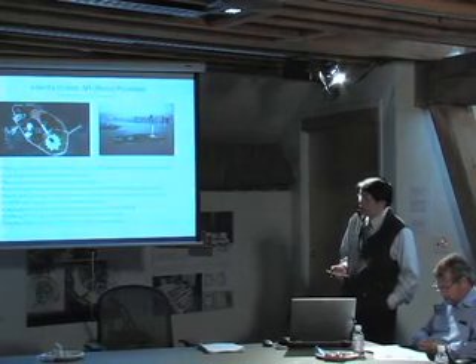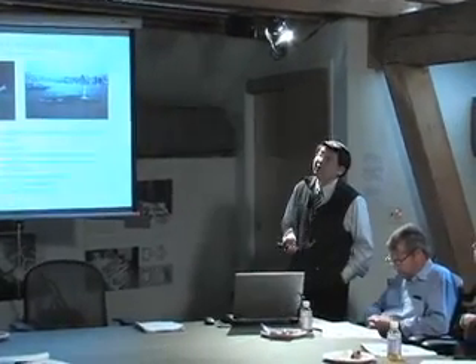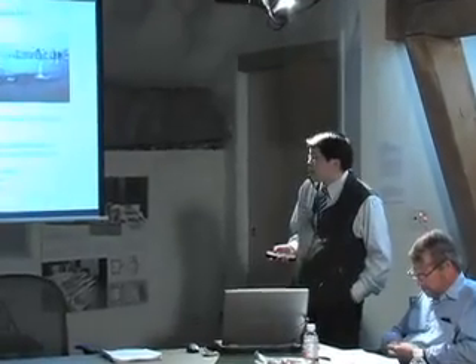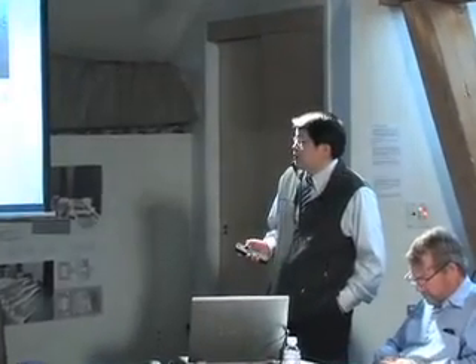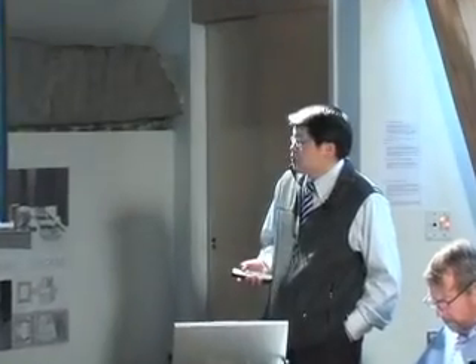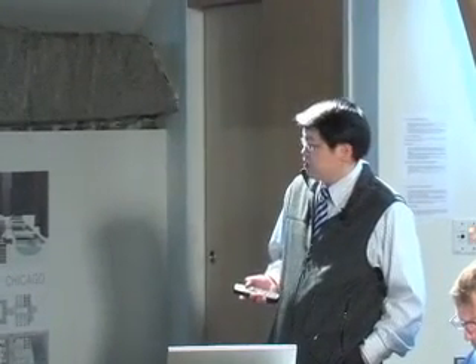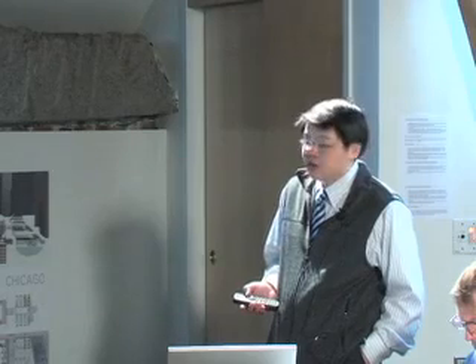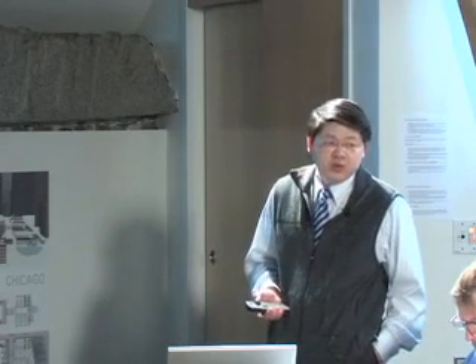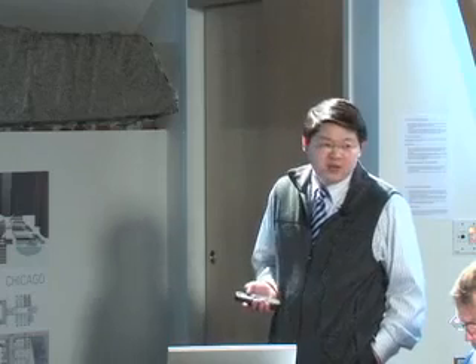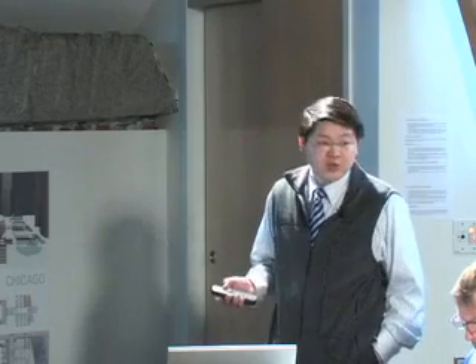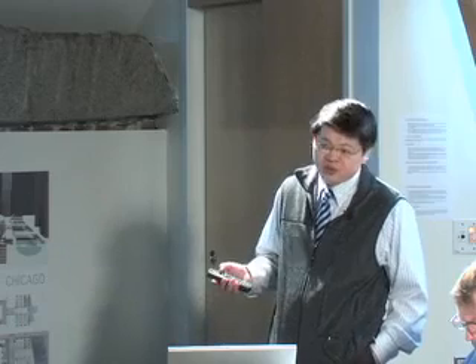It's an open loop standing column well system. They drilled 1,550 feet deep, 8-inch boreholes, not 6-inch. Well, actually, 8-inch boreholes. And because it's an island, they had to use a barge to transport the drill rigs and all the equipment to the island. As you can see, it's only a 7,000 square foot facility. The cost is $700,000, $100 per square foot. But maybe it's worth it, considering the location, you know. Otherwise, you would have to build cooling towers, and nobody wants to see that in that location.